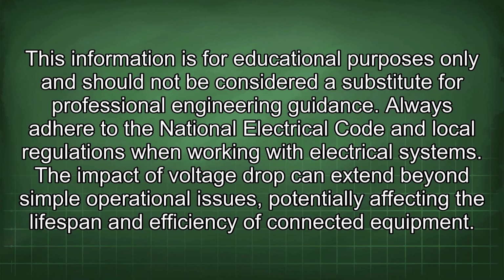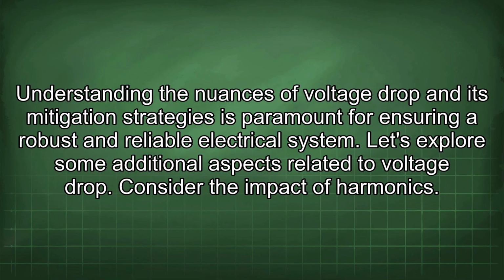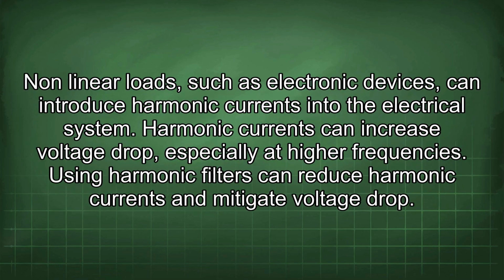The impact of voltage drop can extend beyond simple operational issues, potentially affecting the lifespan and efficiency of connected equipment. Understanding the nuances of voltage drop and its mitigation strategies is paramount for ensuring a robust and reliable electrical system. Let's explore some additional aspects related to voltage drop. Consider the impact of harmonics. Nonlinear loads, such as electronic devices, can introduce harmonic currents into the electrical system. Harmonic currents can increase voltage drop, especially at higher frequencies. Using harmonic filters can reduce harmonic currents and mitigate voltage drop.